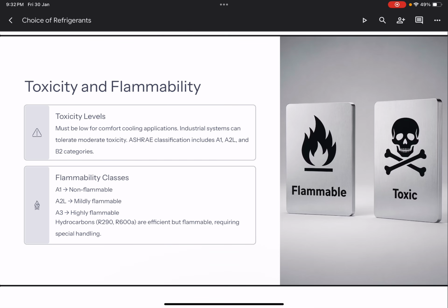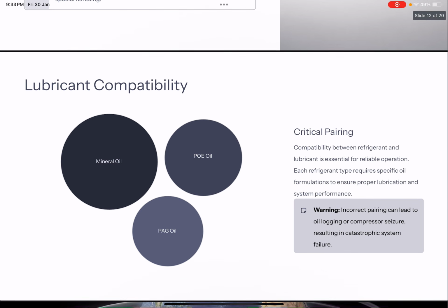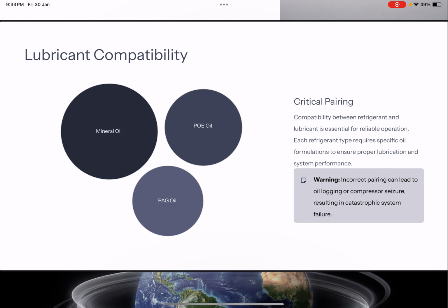Toxicity could also be important in the selection of refrigerants. Industrial systems can tolerate moderate toxicity, but for comfort air conditioning, a very low toxicity is important. So, in that case, again, the ASHRAE classification is important to make sure that the less toxic refrigerant is selected for the household or comfort application, and a relatively toxic refrigerant might be selected for industrial application.